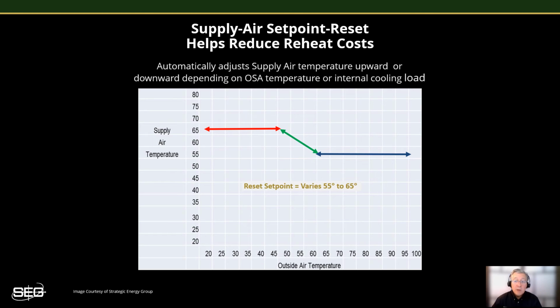A better, more complex strategy is becoming more popular these days, which continually monitors the building's heating and cooling loads, watching either the average building temperature or the cooling valve positions out at the air handlers. It then adjusts the supply air set point automatically, upward or downward, to better meet the needs of the zones as the cooling and the heating loads change throughout the seasons, as well as day to day. As the various zones begin to call for cooling, it provides supply air just cool enough to meet the cooling needs. As a result, it continually helps to save energy by minimizing the need for reheating out at the zone terminal boxes.